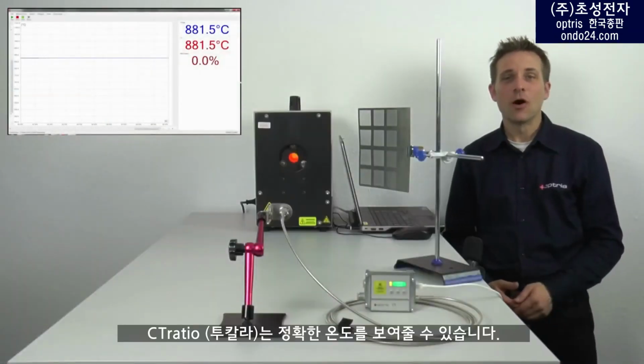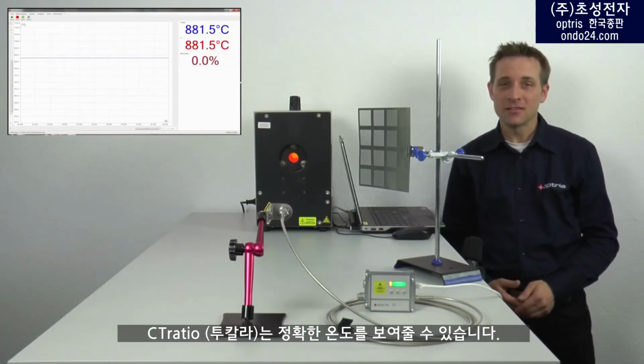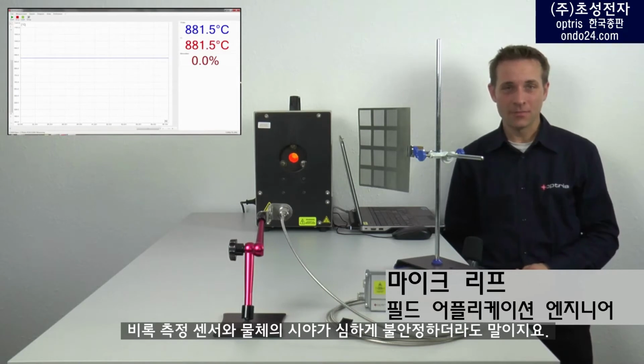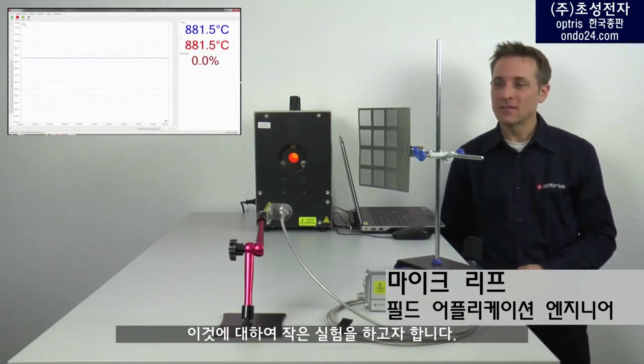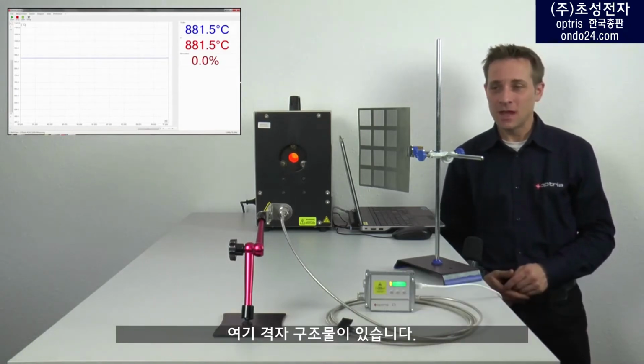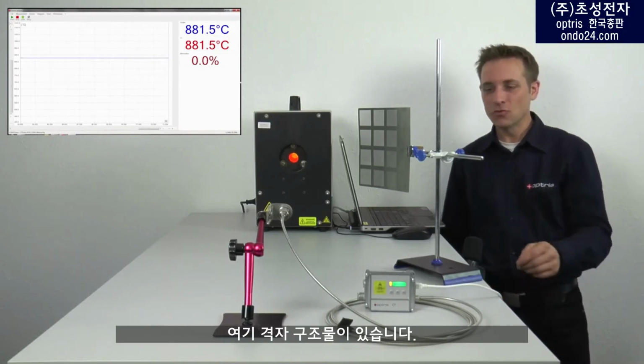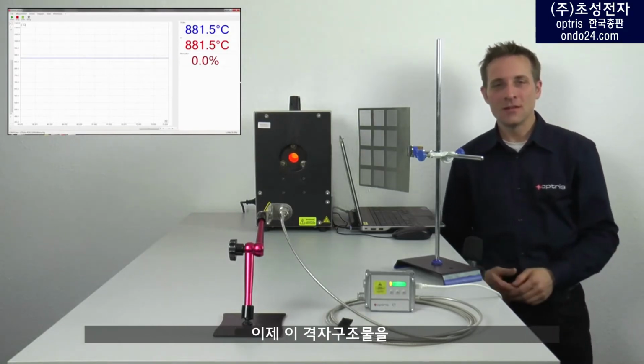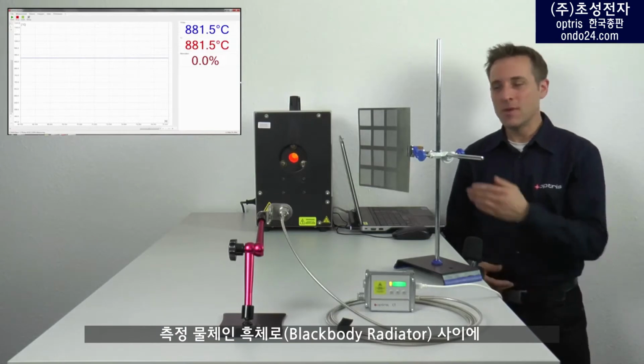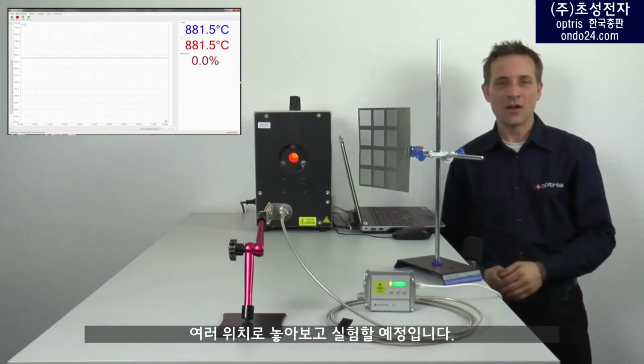The CT ratio can still indicate the correct temperature, even if the view between the sensor and the object is compromised significantly. We can demonstrate this here with a small experiment. I have a matrix of grid structures here, and we will set various grid structures between the sensor and our measurement object, which represents the black body radiator.